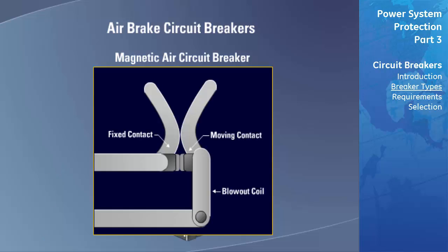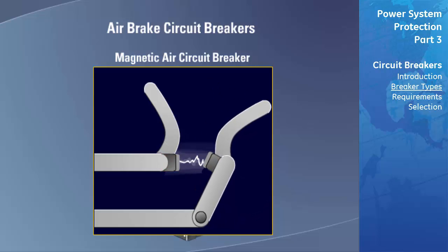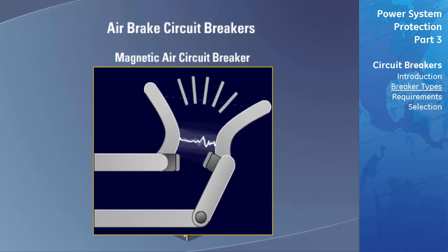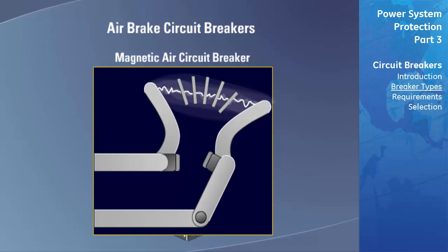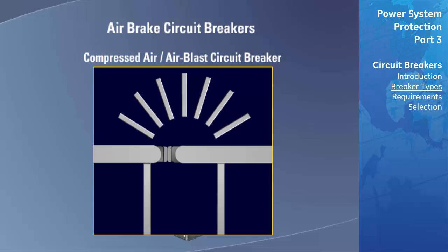The magnetic air circuit breaker interrupts the arc between two separable contacts with the aid of magnetic blowout coils. As the current-carrying contacts separate during a fault condition, the arc is drawn out horizontally and transferred to arcing contacts. The blowout coil provides a magnetic field to draw the arc upward into the arc chute, where it is elongated and divided into many small segments. Compressed air circuit breakers depend on a stream of compressed air directed toward the separable contacts to interrupt the arc.